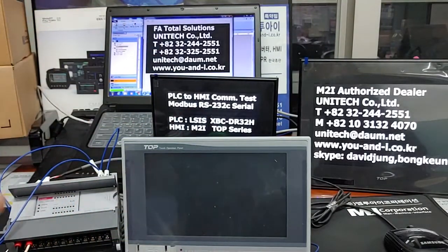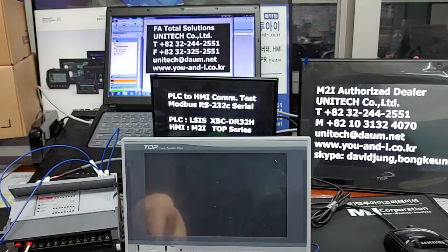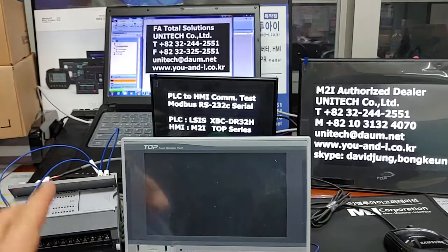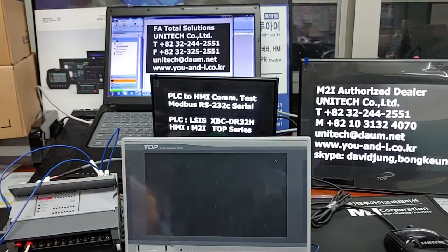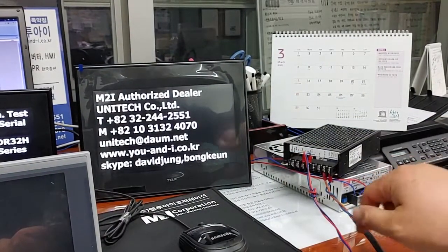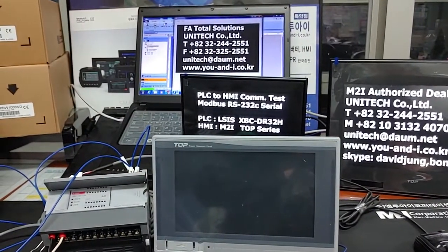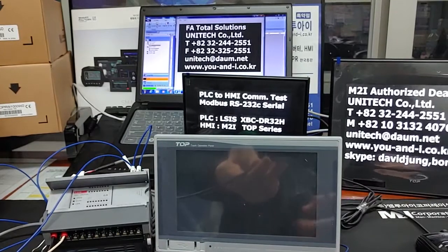For smooth progress, I set it up in advance. We've had RS-232C serial communication wire between touch panel and PLC. In addition, the touch panel and PLC were powered through SMPS. There are two SMPS here — one SMPS is for the HMIs behind, and the other is for the HMI in front of the camera. PLC power is 220VAC and touch panel control power is 24VDC — that's why two power supplies are needed.